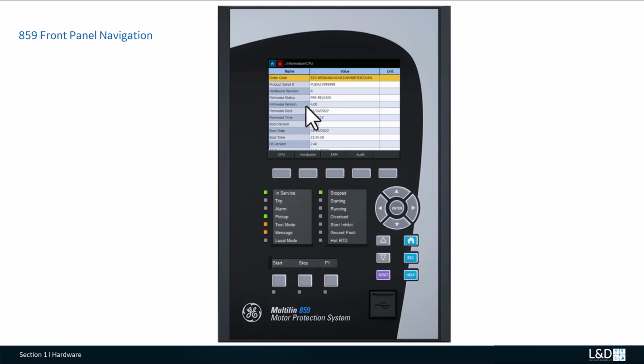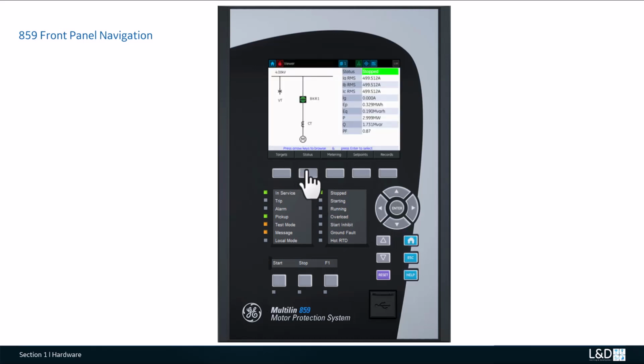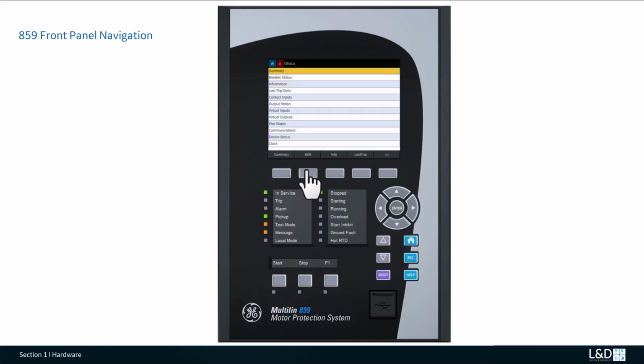and we can also see the firmware information. And if you click this down arrow key button, you can see more information like the MAC address, etc. So now we can go back and check the other status. We can check the status of the contact inputs, the relays, the breaker status. You can just use this down arrow key to highlight and check each one's status.